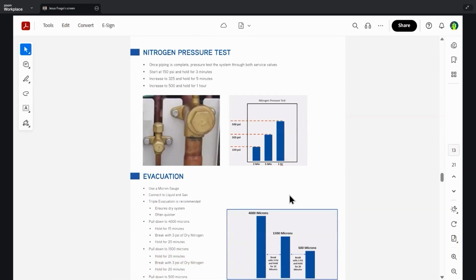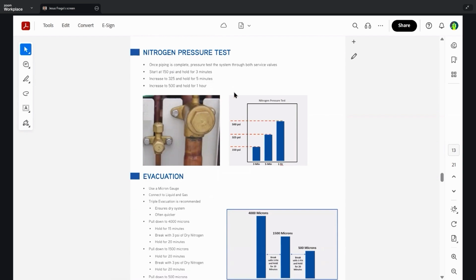Moving on, the nitrogen pressure test. This is another one of those things that pretty much stays the same. Once the piping is complete, pressurize the system through both service valves. Start at 150 and hold for 3 minutes. Increase to 325 and hold for 5 minutes. Increase to 500 and hold for 1 hour. And here's a chart on how to do that. Duration, examples.